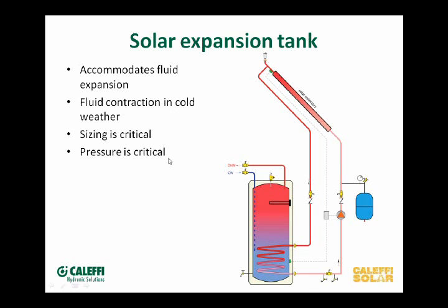If you're going to fill your system up to 60 pounds, you have to take the cap off the expansion tank and pre-charge it to that same pressure. Our Caleffi solar tanks come with about 70 pounds of pre-charge already in them because they're made in Europe assuming systems will be pumped up to 60 pounds. They come filled with nitrogen, not just air, so it doesn't permeate through the EPDM bladders like oxygen will. By coming with that high pre-charge, you can just bump it down to 60 pounds instead of having to add nitrogen.